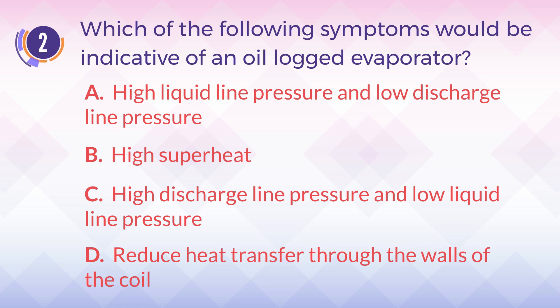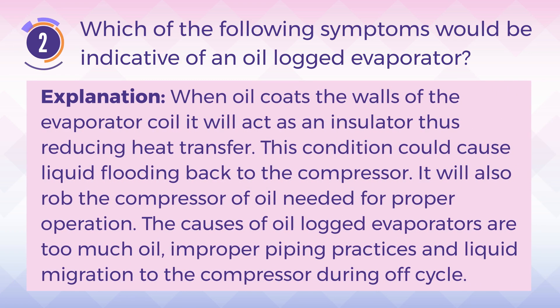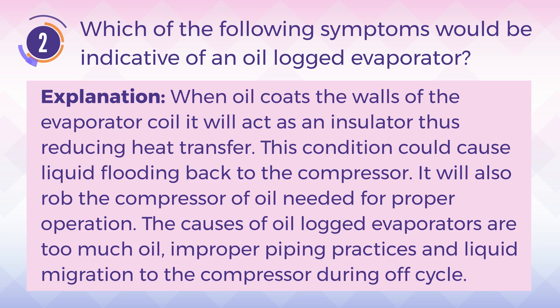The answer is D. Reduced heat transfer through the walls of the coil. Explanation: When oil coats the walls of the evaporator coil, it will act as an insulator, thus reducing heat transfer. This condition could cause liquid flooding back to the compressor. It will also rob the compressor of oil needed for proper operation. The causes of oil-logged evaporators are too much oil, improper piping practices, and liquid migration to the compressor during off-cycle.